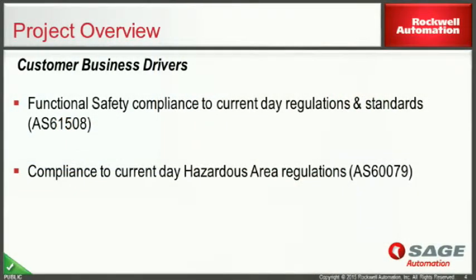Also, there was a focus on functional safety compliance. So our customer chose to implement a 61508 functional safety compliant system. Our new system had to comply with those requirements from outcomes of HAZOPs that were undertaken by the customer, LOPA studies, and our safety system complied with all those requirements.